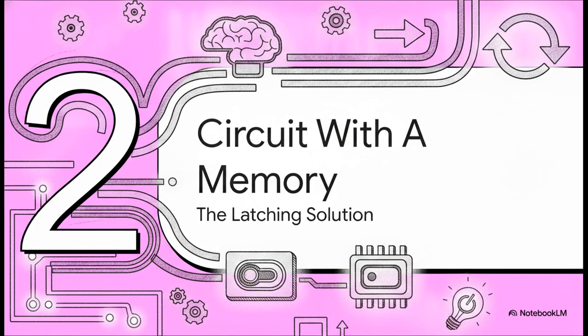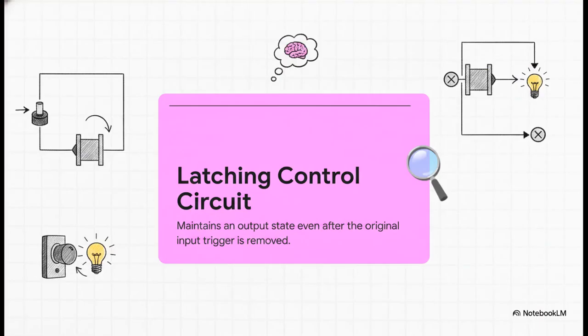Which brings us to part two, the circuit with a memory, the latching solution. Enter the Latching Control Circuit. What's so cool about this concept, sometimes called self-holding or lock-in, is that it maintains its output state even after that original input trigger is completely gone. Simply put, it's an electrical circuit with a literal memory. Once you tell the circuit to turn on with just a quick momentary press, it remembers that command. It locks the electrical path closed and stays on indefinitely. It will not turn off until it gets a completely separate, explicit command telling it to turn off.